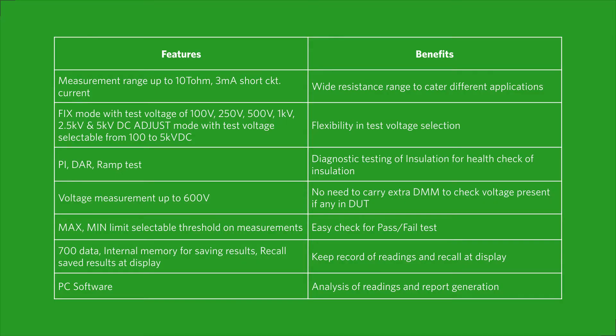Let us see the features and benefits offered by Rishinsu 5DX. Measurement range up to 10 Tera-Ohms. 3 mA short circuit current for wide resistance range to cater to different applications. Fix mode with test voltage of 100V, 250V, 500V, 1KV, 2.5KV, and 5KV DC. Adjust mode with test voltage selectable from 100 to 5KV DC for flexibility in test voltage selection.